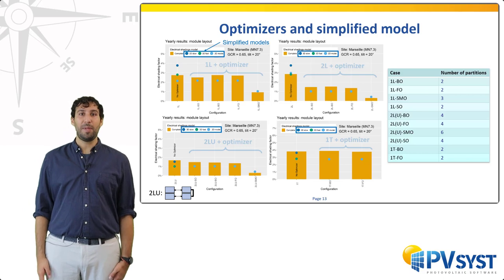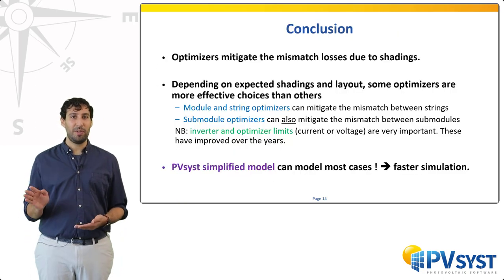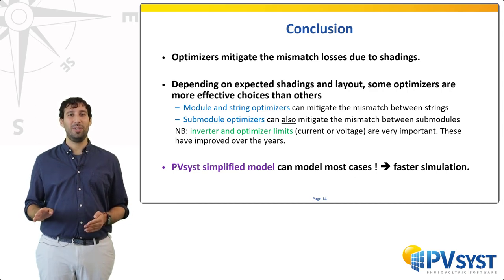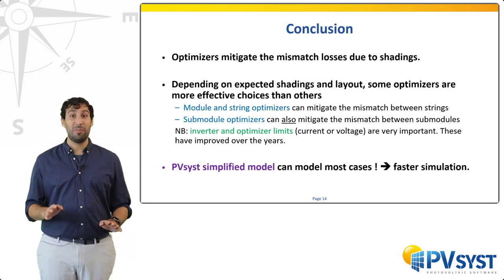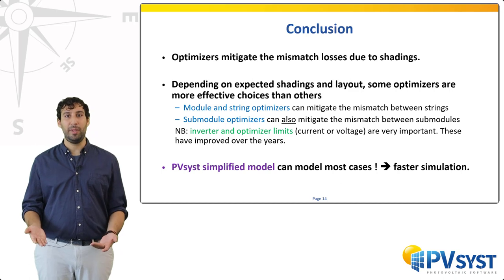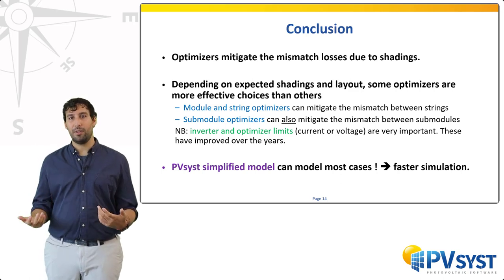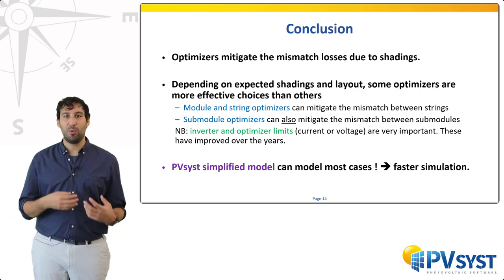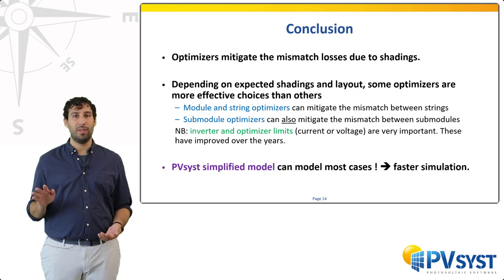To conclude, optimizers are effective at reducing the mismatch due to shadings. Depending on the system layout, some optimizer choices are more effective than others. Typically, whenever the shadings are regular, all types of optimizers can reduce the mismatch between strings. Submodule optimizers can even go a bit further and help recover the power from some diffuse irradiance. When designing a real system, it is important to consider cost and efficiency reduction, as well as extra limitations of the components — in this study we just focused on the shadings. Ultimately, factors like the inverter and optimizer limits are quite important to take into consideration. Finally, we have shown that in PVSyst, most situations can be modeled with a simplified model as well, unlocking the ability to simulate large regular systems in less time.